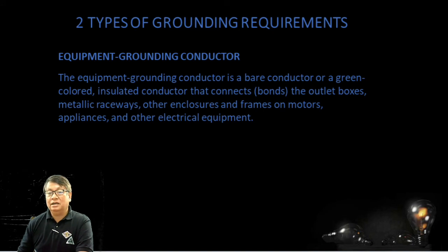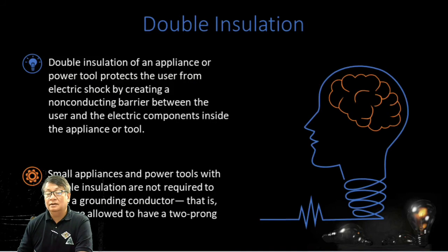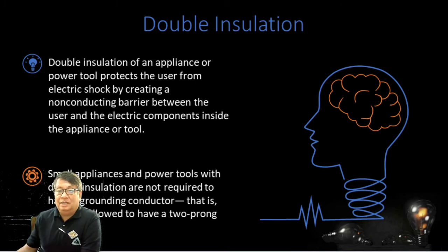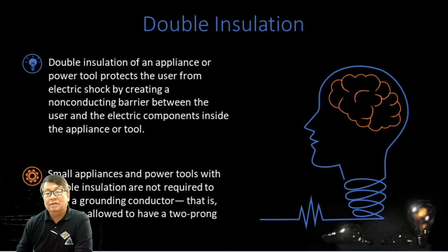Equipment grounding conductor is a bare conductor or a green-colored insulated conductor that connects the outlet boxes, metallic raceways, other enclosures, frames of motors, appliances, and other electrical equipment. So, double insulation of an appliance or power tool protects the user from electric shock by creating a non-conducting barrier between the user and the electric components inside the appliance. So, diyan po natin makikita na it's very important to have this double insulation. Small appliances and power tools with double insulation are not required to have a grounding conductor. That is, they are allowed to have a two-prong plug.